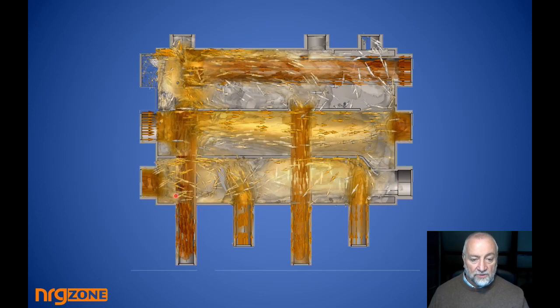So here we have the scenario. You can see the water being taken back by the heat pump, delivered back in here, straight across, straight out to the gas boiler. The water was moving through a much wider space here, so even though it's a lighter color, it's because the volume of water moving is in a bigger area, but then it's concentrated here as it passes through the socket, so the speed increases, and then it's delivered at the same rate that's passing here. It has to pass here, and now you can see the heat being taken away again.